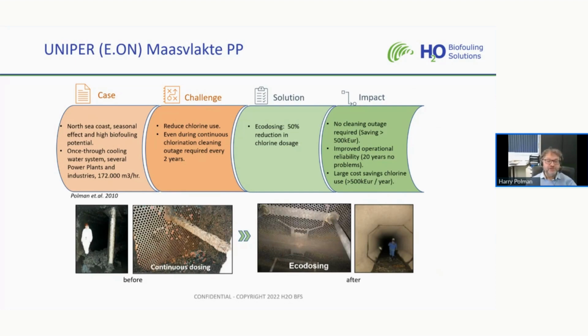Before Ecodosing, they had a continuous dosing, and as you can see, with the continuous dosing, there was still fouling in the system. They had an outage every 2 years to clean the whole system by hand, which was very costly, because the plant could not produce power. In 1998, we tailored the dosing and switched from continuous to Ecodosing. We reduced the amount of chlorine dosed by about 50%.